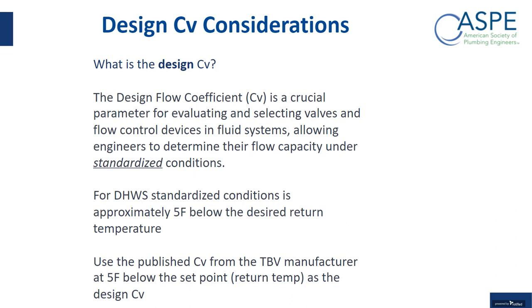The other issue is, what is the design CV? The design flow coefficient is a crucial parameter for evaluating and selecting valves and flow control devices in fluid systems. It allows engineers to determine flow capacity under standardized conditions. What I typically use for a domestic hot water system, I always select a design CV based on 5 degrees Fahrenheit below your return temperature. So if your return temperature is 120, I would say that your design CV should be at 115.